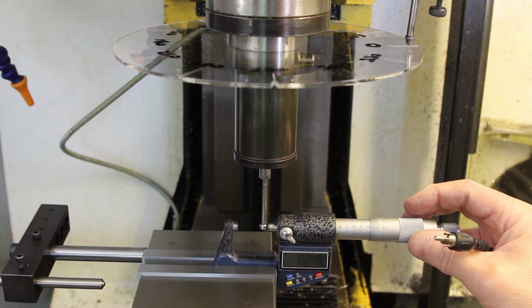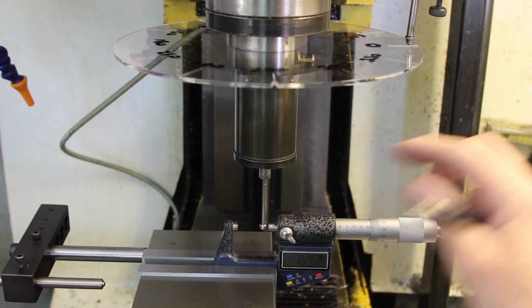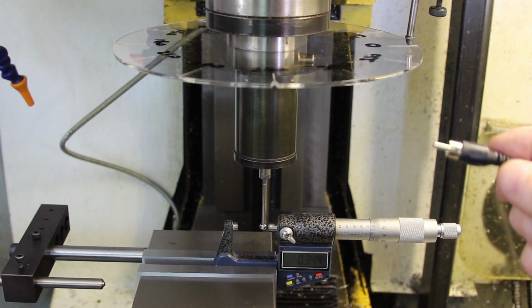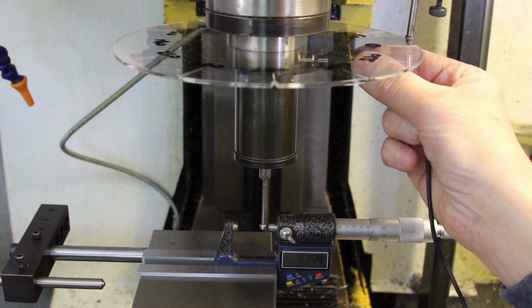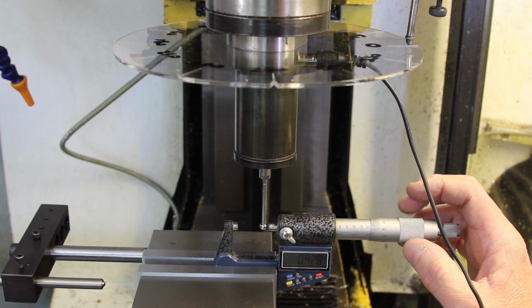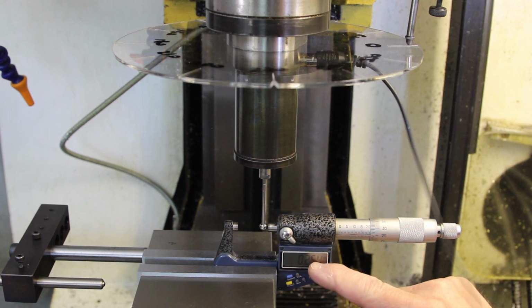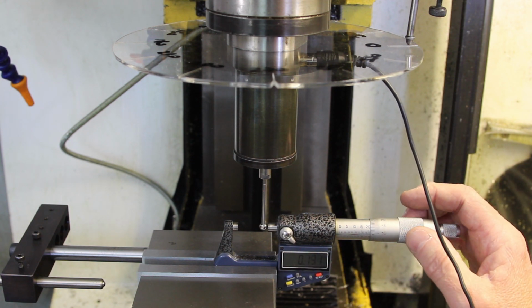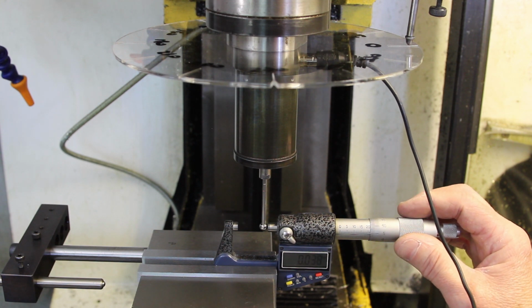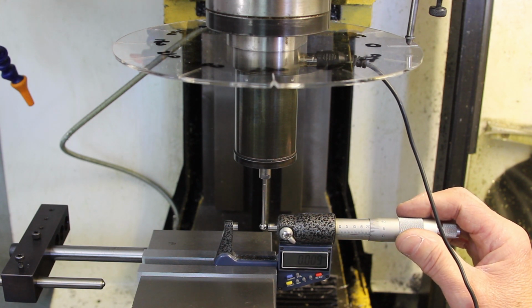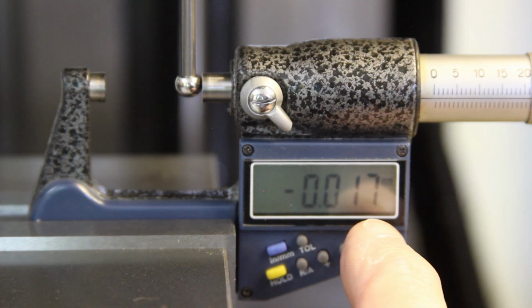Now we know that advancing the thimble until we hit 0, that's where we actually make connection with the probe tip. So now if I plug my DMM into the actual probe output, so now I can advance the thimble. When we hit 0 on here, we know that that's the point where we've touched the ball, or the ball on the stylus, and then it's a question of how far we go before we make the break. There we go, about 0.017 of a millimetre.